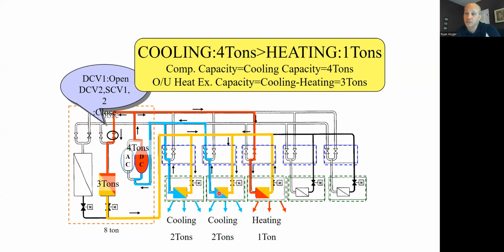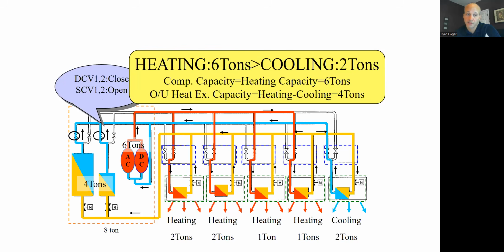Somewhere I need 4 tons of condenser coil surface area. 1 ton of condenser coil is going to be over here in this room that wants heat. The other 3 tons goes outside. So I'm going to get a total of 5 tons of heating and cooling capacity by operating my compressor at only 4 tons, and for the heat rejection price outside, fan energy out there and so forth, of only 3 tons. Instead of running a 4-ton cooling and a 1-ton heating.